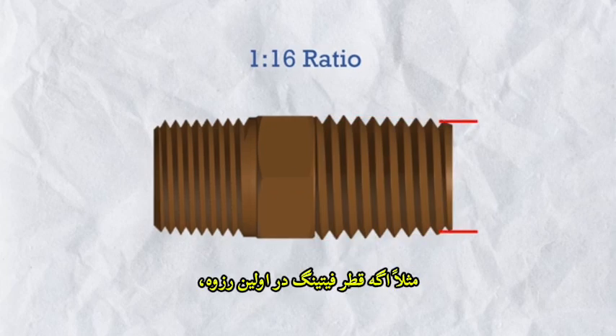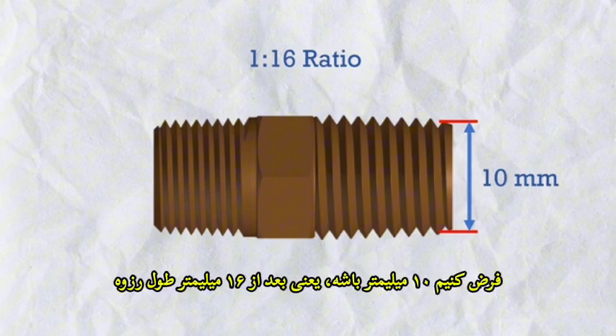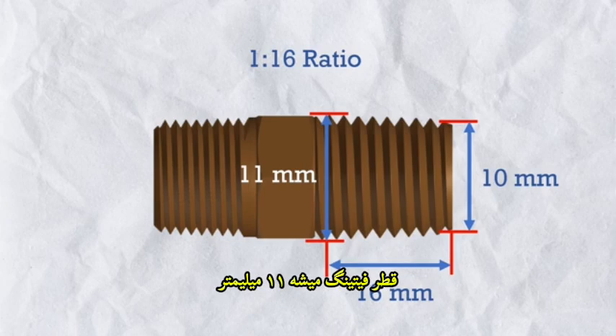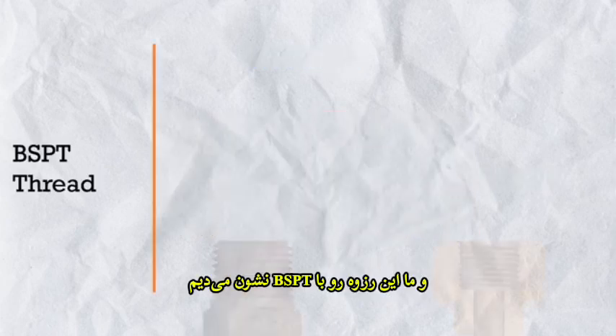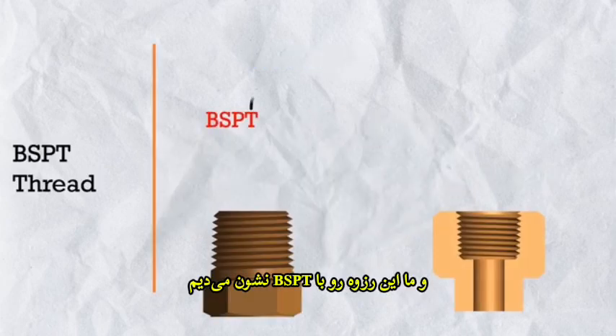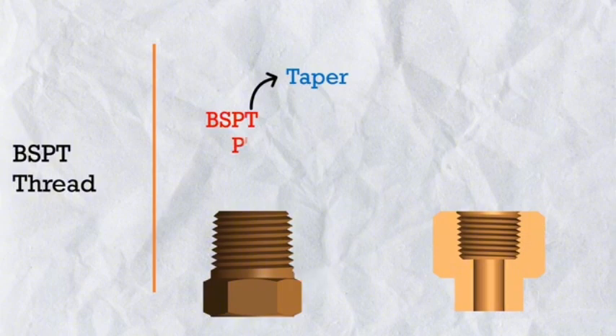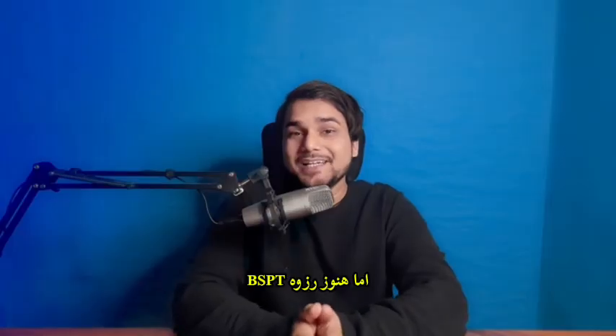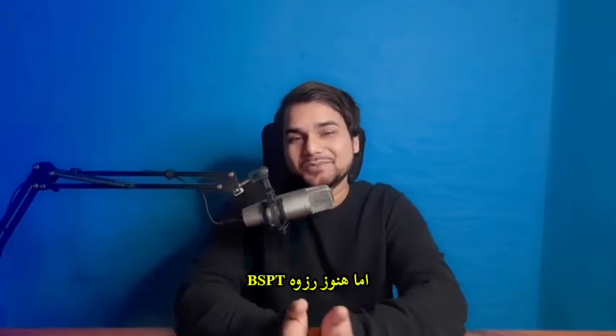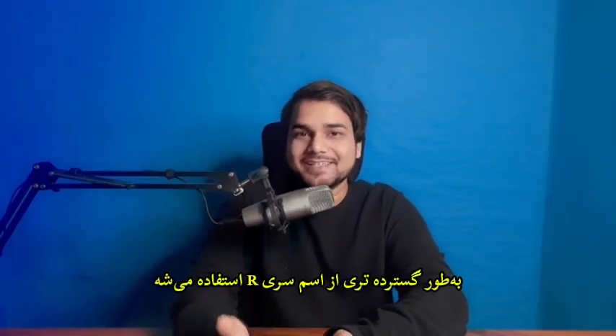For example, if the first thread diameter is, let's say, 10 mm, after 16 mm along the length, you will get an 11 mm diameter of the thread. And we denote this thread by BSPT or PT, which also has been obsolete and got replaced by the R series. But we still use BSPT thread widely as well as R series thread.